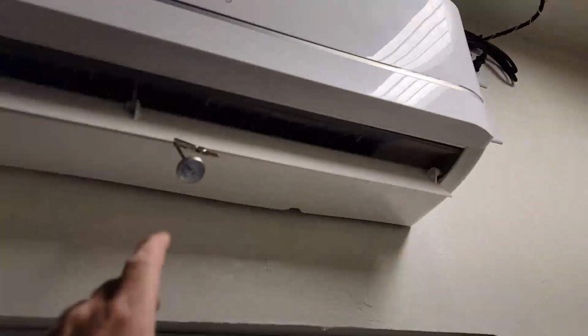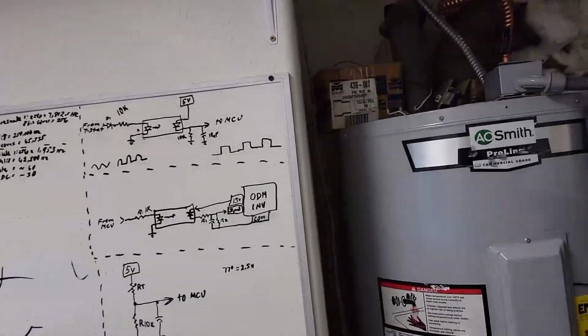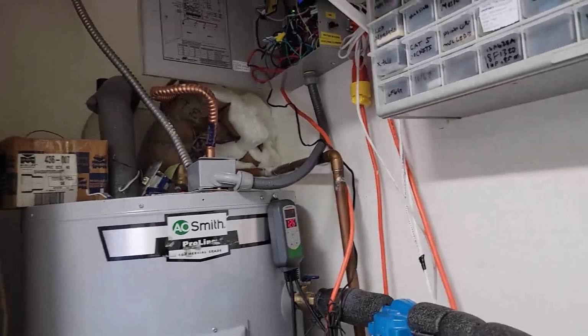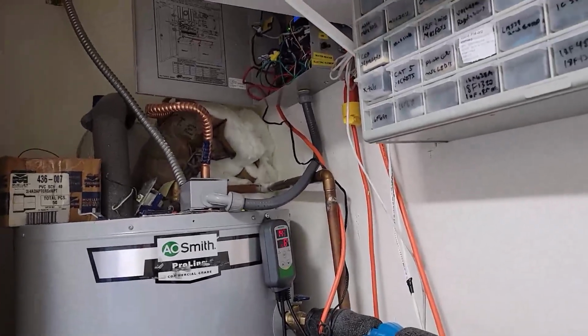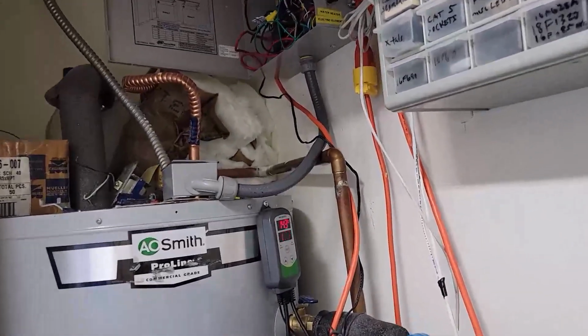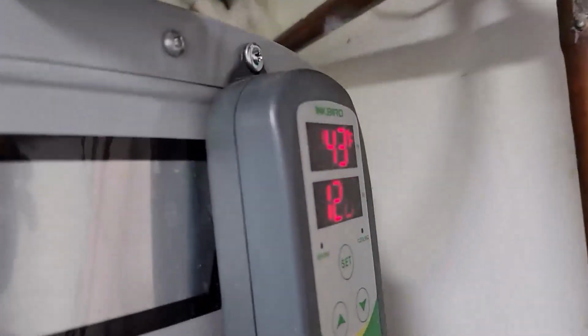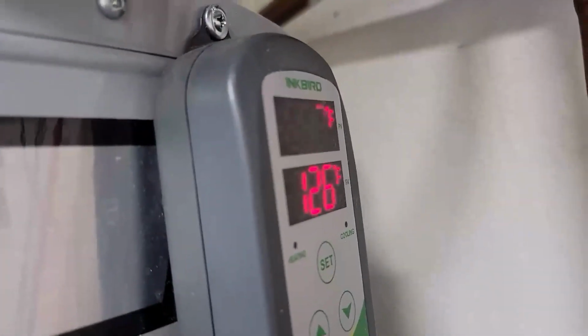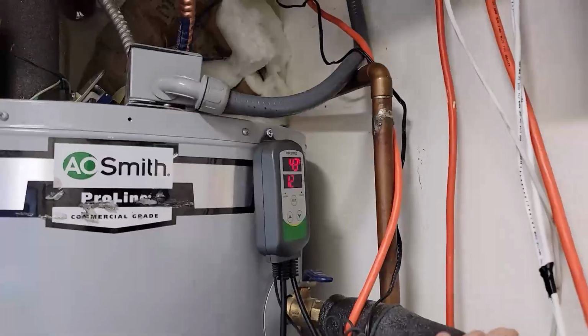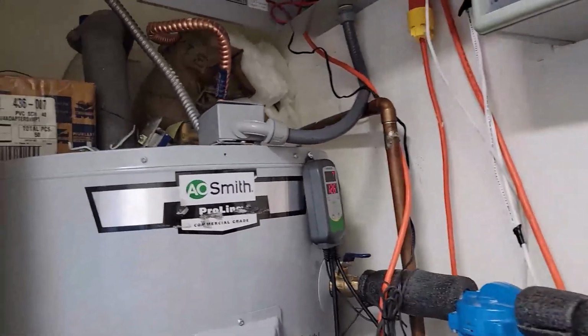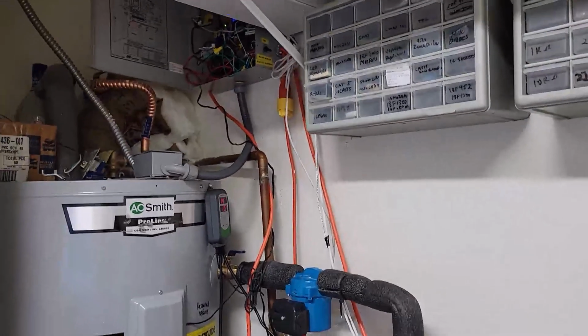So I've been in here working on some electronics, letting this unit try to maintain this room at 78 degrees. It was blowing out nice, crisp 60 degree air, but this room has quite a bit of heat, I guess, so it wasn't dropping much below that. And it did just satisfy, but look how warm the water heater is. 143, and the set point in here is 126. But I think it can handle that. So that's a pretty good test. It ran for over a solid hour while I was in here. And that's as hot as the tank got.